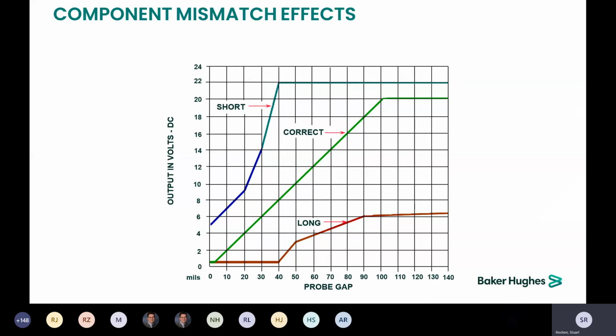We have a mod for the 8mm probes to allow up to a 13-meter length, and we had a customer that used that mod, and they ended up with a 12.5 meter system. So they got a 12-meter extension cable and a 0.5 meter probe. They should have installed a 1-meter probe. And there was a 30+% difference from actual vibration to what was being reported. And since it was short, it was reporting 30% higher vibration than the machine was actually showing.